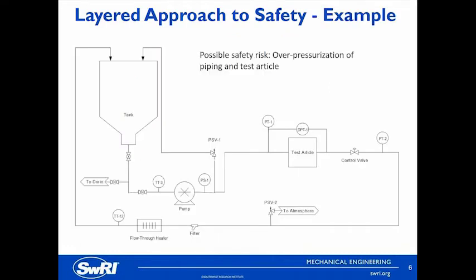Now I'm going to go through a basic example. This is a very simple process and instrumentation diagram — we call them P&IDs. Here you can see a tank. The purpose of these diagrams is to show the general layout of the equipment, not the physical location of everything. It shows that the pump comes first, then the test article, etc. Fluid flows from the tank through the pump, past a temperature transmitter upstream and a pressure switch downstream, through a test article, a control valve where you might meter or control the pressure and flow rate, downstream pressure, then through a filter and maybe a flow-through heater. We can assume this is a positive displacement pump that will continue to build pressure if a flow path is blocked. So our possible safety risk here is overpressurization of the piping and the test article.